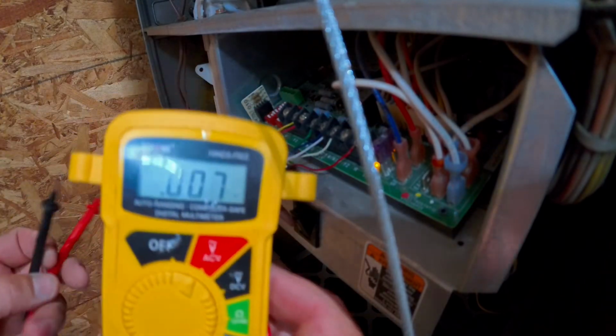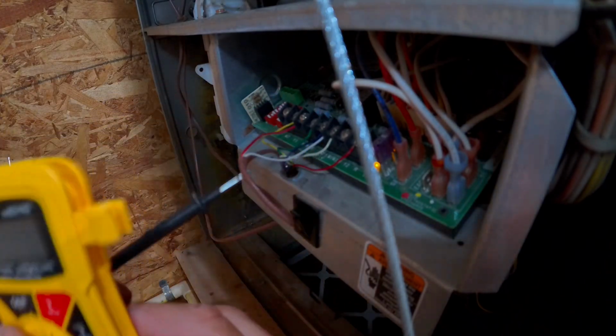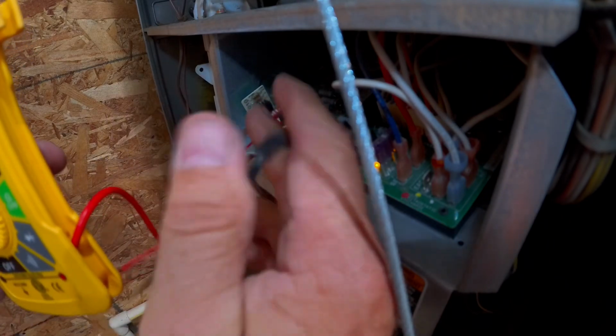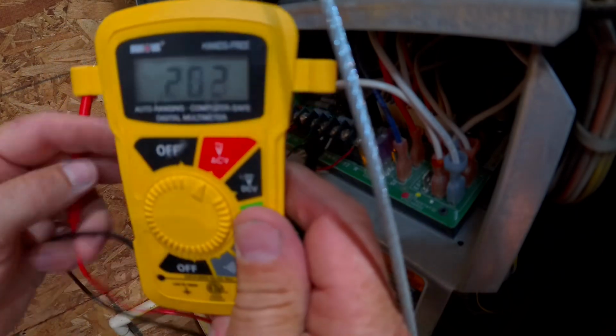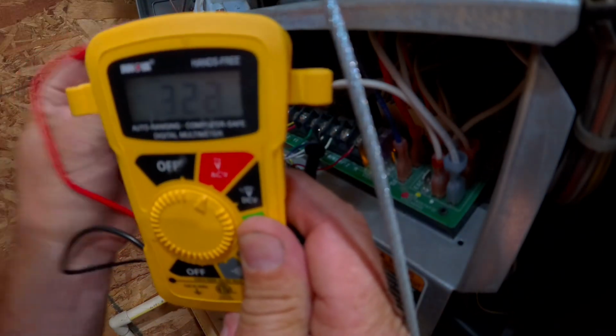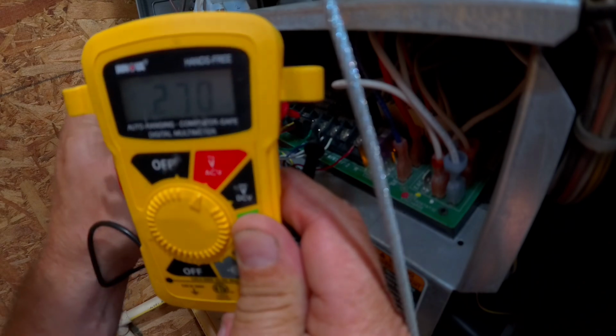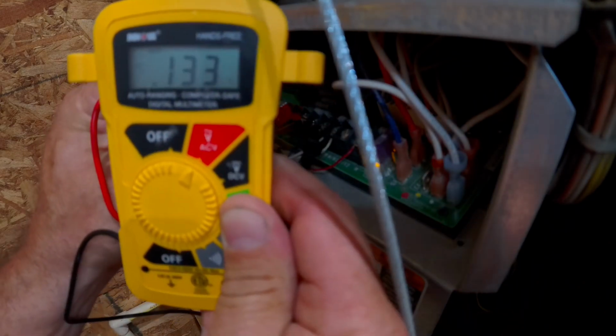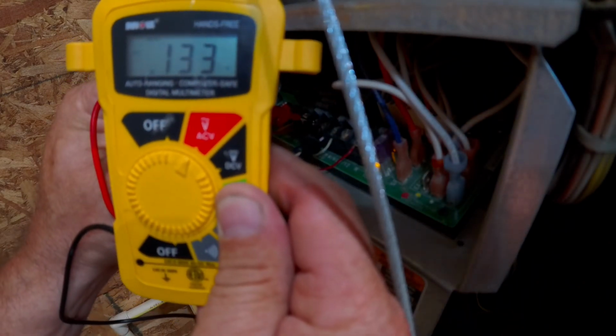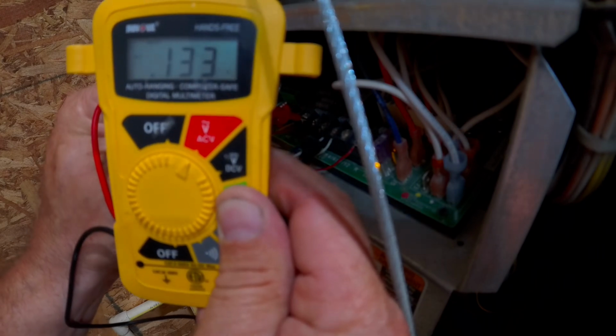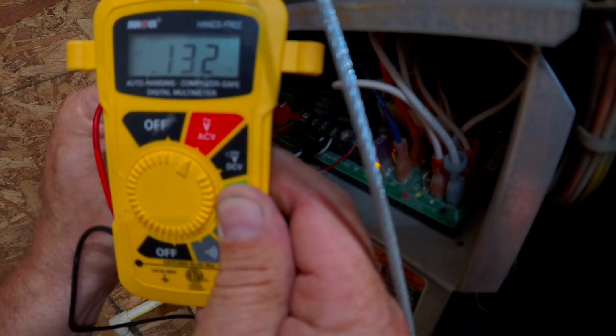So again, with our meter set to AC voltage, we're going to use the black lead, and we're going to go to the common. This is difficult to do while trying to show it on camera. So we got the common, and then we're going to check the red one to the green wire, which is the fan on. And as you can see, we've got no voltage, 0.133 volts. So the thermostat is not telling the fan to turn on.